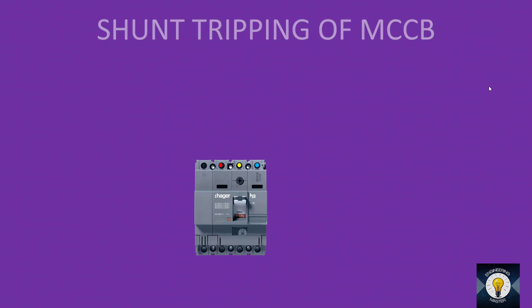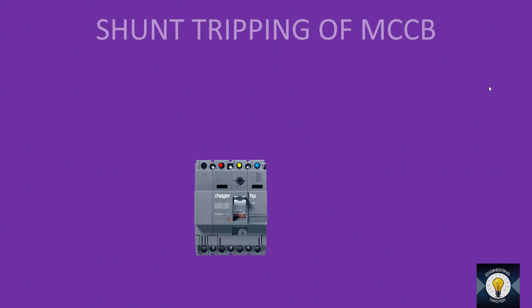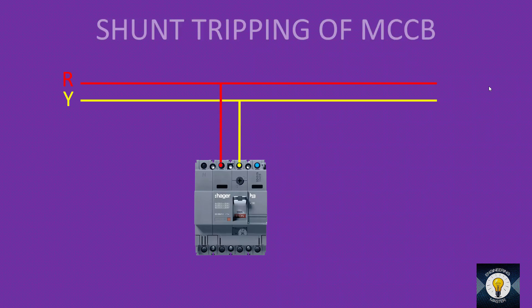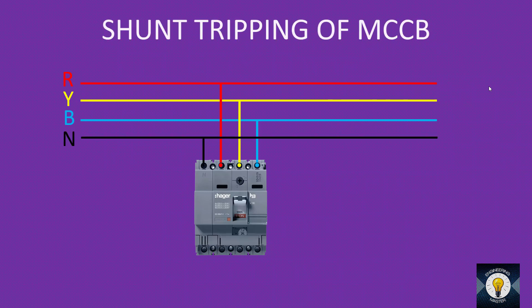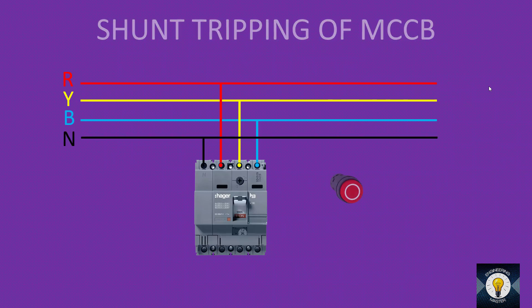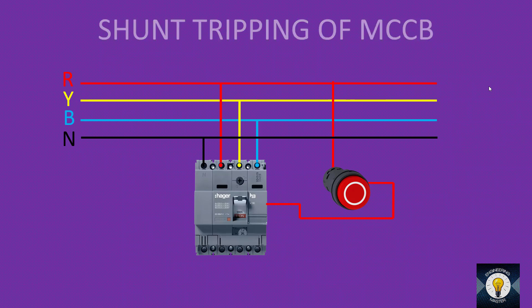Shunt tripping or remote tripping is possible in MCCB. To wire it: connect three phases R, Y, B and neutral N to the MCCB. Take an emergency push button switch, connect a phase to it, and that wire connects to the shunt terminal of the MCCB. Connect neutral as well. This is the basic wiring for shunt tripping.